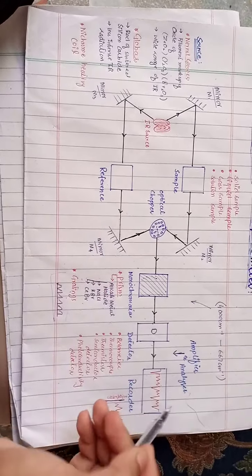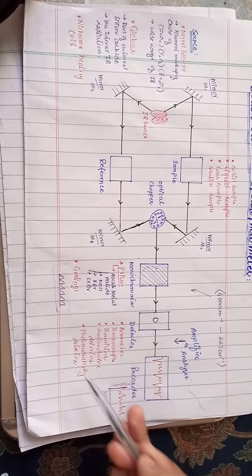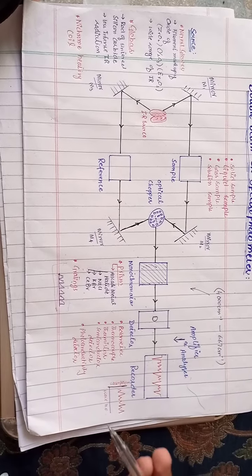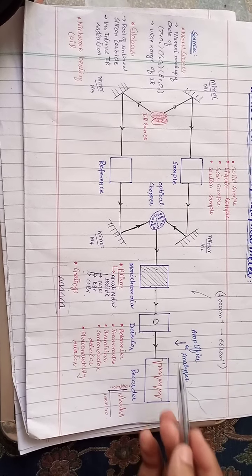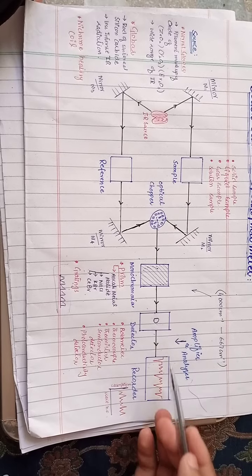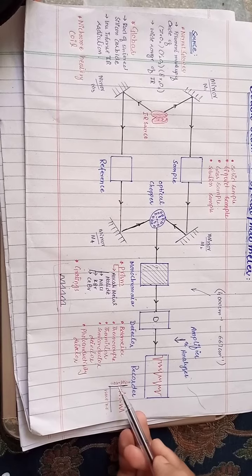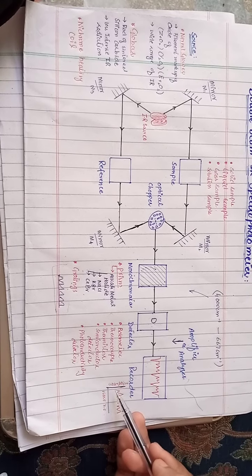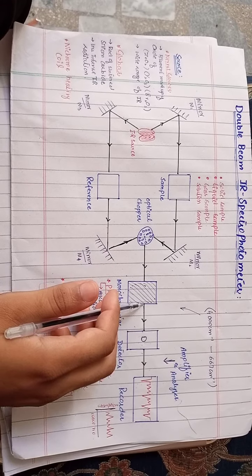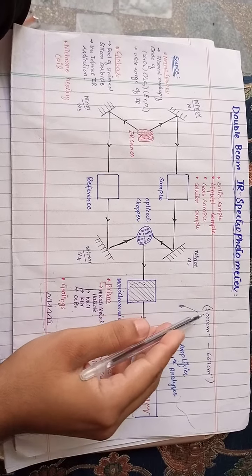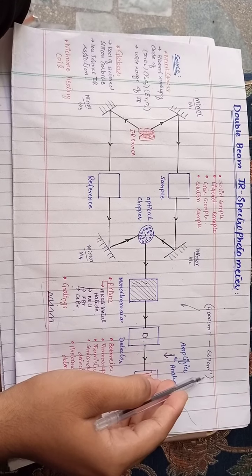Now the next component is the detector. The detector may be a bolometer, thermocouple, thermistor, semiconductor or photoconductivity detector. And the last one is the recorder. There the radiation coming from the detector is recorded on the basis of the wave number and absorption value. The beam transferred from the monochromator to the detector has a range of 4000 cm inverse to 667 cm inverse.